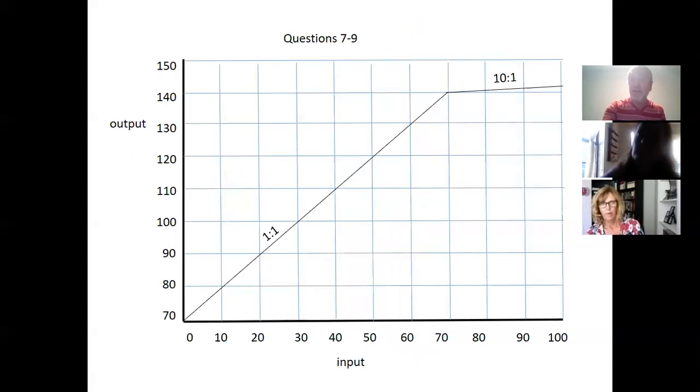Whereas this one, two things are different. Higher knee point, higher ratio. It waits to go into compression and then it slams on the brakes. So here is the ceiling, limiting the ceiling. Instead of providing maximum gain for soft sounds, this is providing maximum gain for soft and medium sounds, but this is meant for a high power hearing aid.